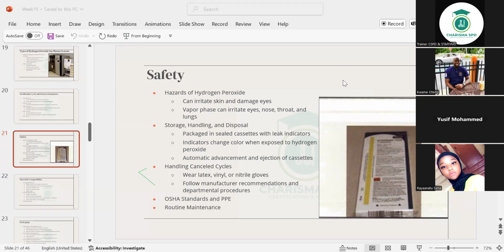When you're putting it in the machine, you open this pack, take the cassette from there, and put it in the slot in the machine. But even while it's packaged like this, not yet used, if there's a leakage, that yellow line is a chemical indicator that is going to change to red. It could be a white line; it's going to turn red, meaning that cassette has a leakage. It's of no use. It's no good. And then you have to take all the safety precautions.